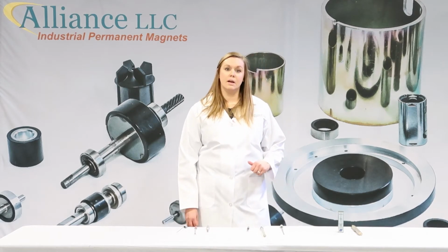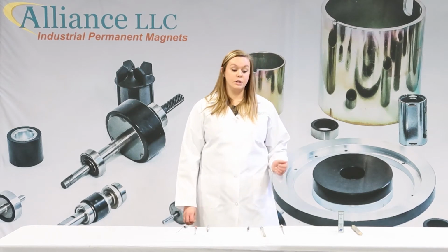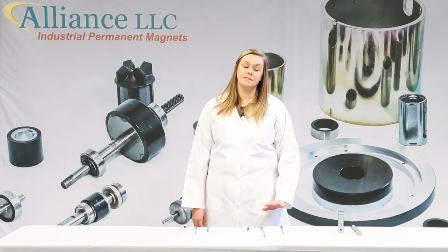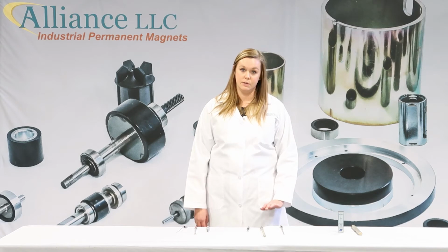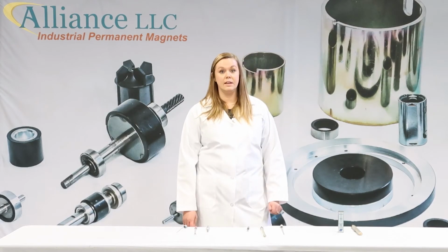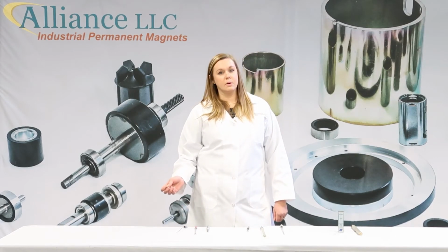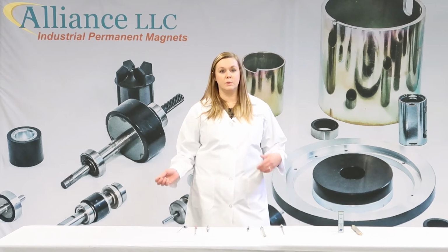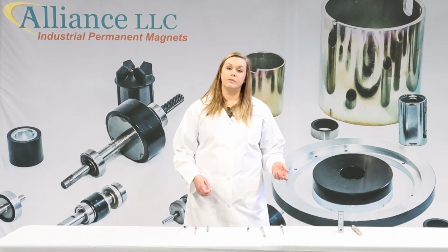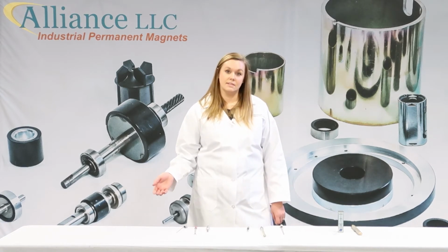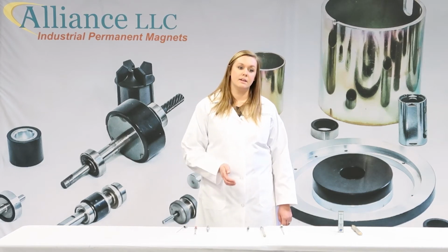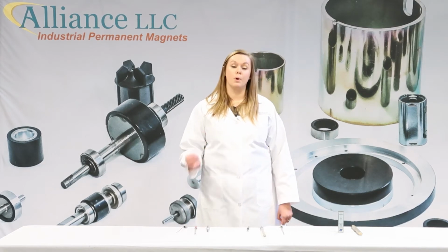And because they can be up to several $100s, you need to make sure that you have a plastic cover to protect your probe from being bent or scratched when not in use. Unfortunately, the manufacturing brands cannot be interchanged with the Gaussmeters and probes. So for example, if you have a Maxis Gaussmeter, you cannot use a magnetic instrumentation probe, or vice versa.